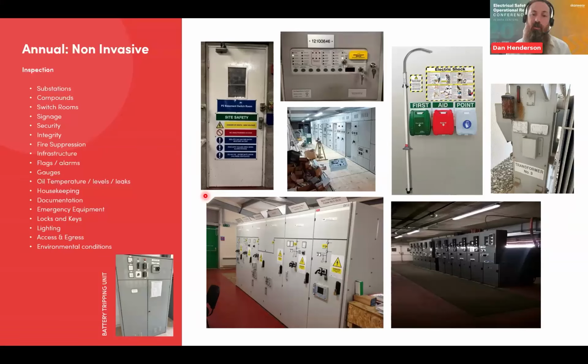A lot of this network's going to be critical to your network. It's difficult for people to firefight, especially with high consequence systems like electrical systems. And if you've got things like oil-filled transformers, you've got potential fuel sources in there, which obviously are sustainable as long as your fire triangle is present. Also, from a storage perspective, people might keep things in there like spares not relevant to the equipment, so it might be relevant to the process.